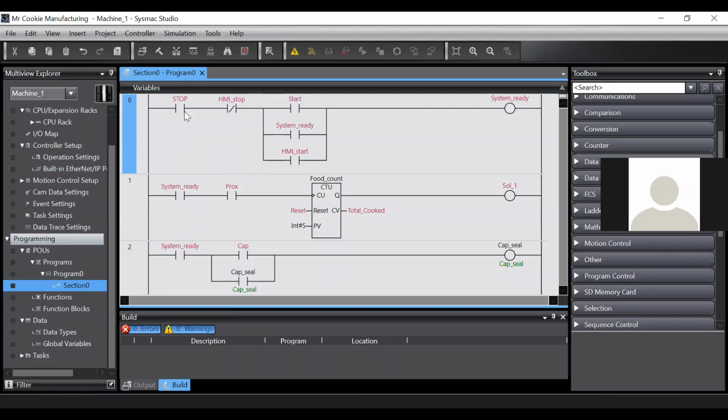That's correct, because all push buttons which are red for stop, mechanical, are normally closed. They're always normally closed. Now, can you have a normally open on a push button? Sure, you can, but 9 out of 10 times you're not going to, because what is the stop supposed to do? It stops something, right?